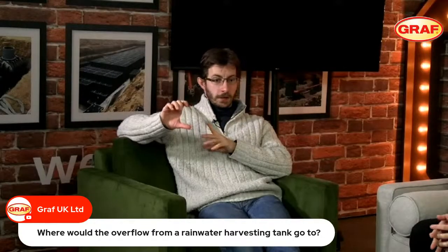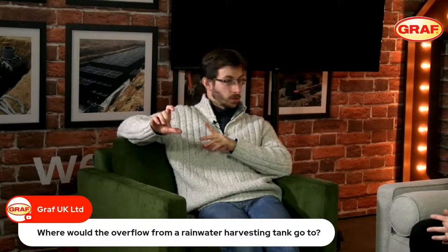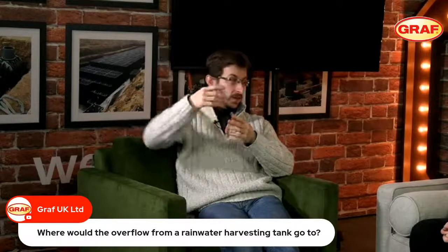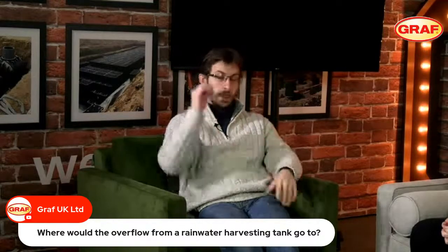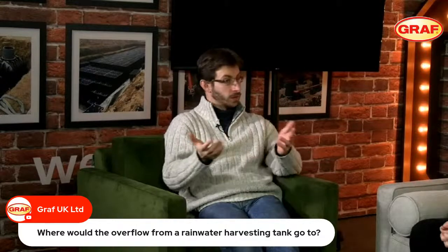Yes. Perfect. And the next one: where would the overflow from a rainwater harvesting tank go to? Okay, now this very much depends on the solution you're discharging to. You would normally go to a soakaway, or you also have the option of a storm drain if there is one local which you can discharge to. You'd normally favour the storm drain if you haven't got any sort of percolation rate from the soil. So with a soakaway option, we would look at testing the permeability, the infiltration rate of the soil, and if there is the space available and there is very good quality soil, we would look to discharge to ground.